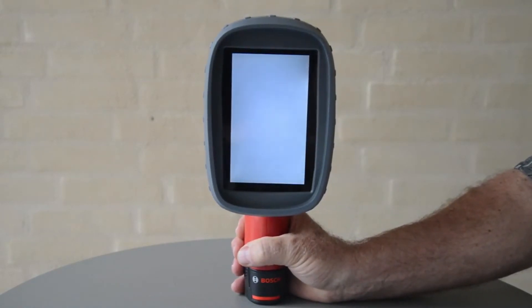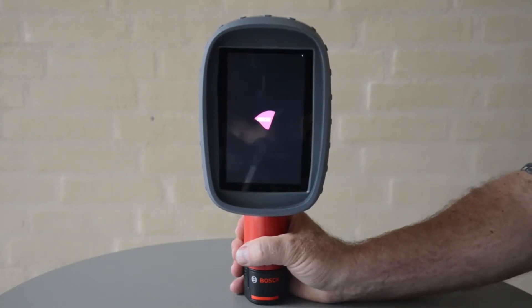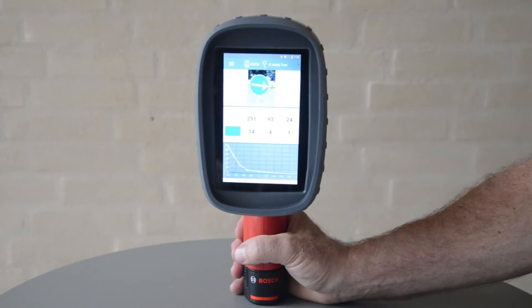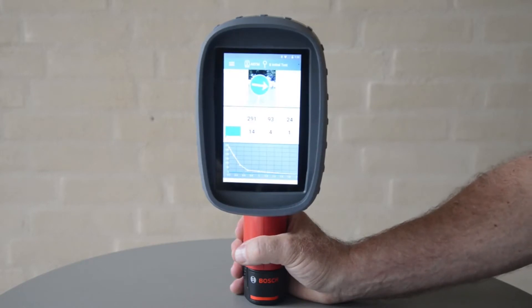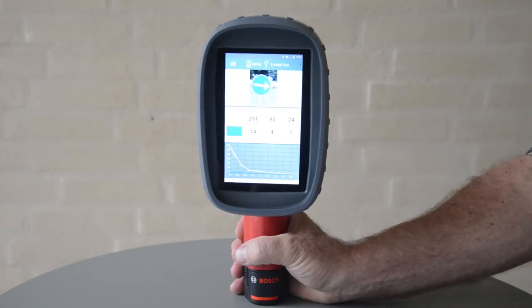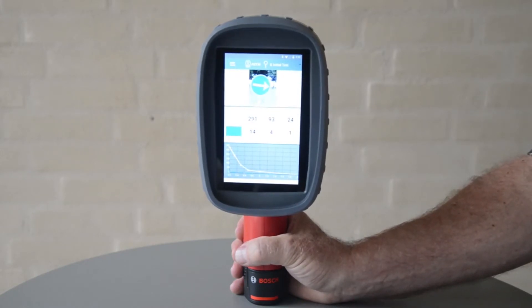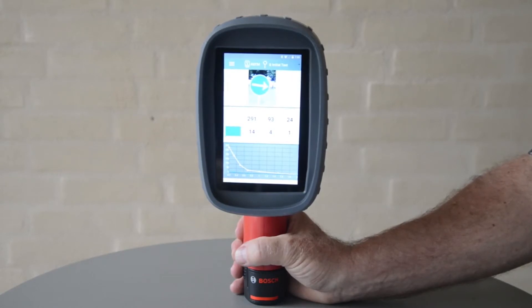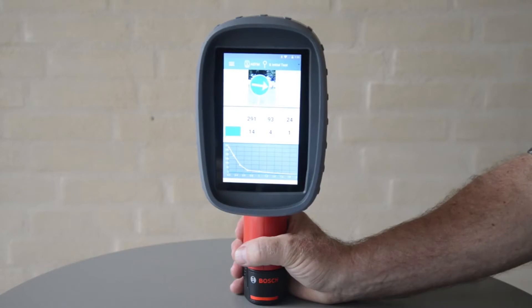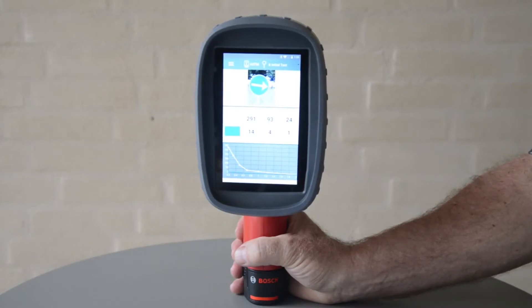After some time the system has booted and the instrument will be ready for use. The GRX automatically switches to standby mode if not used for a period of time. The length may be adjusted under settings. From standby mode the instrument is ready within 1-2 seconds.